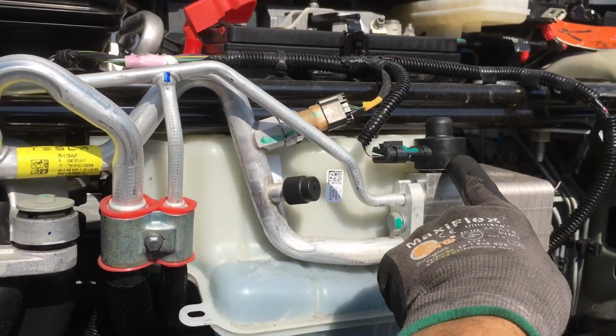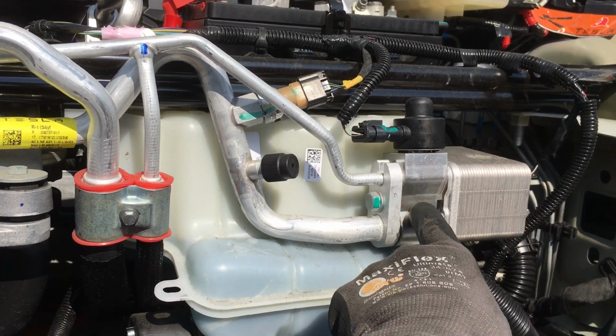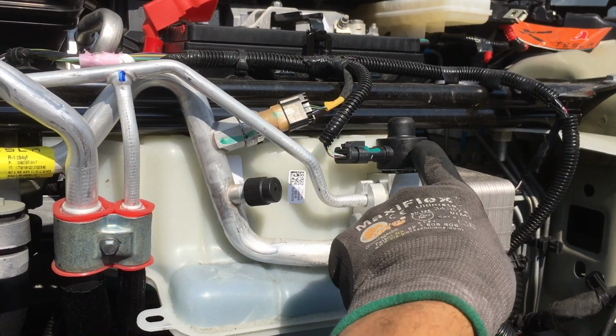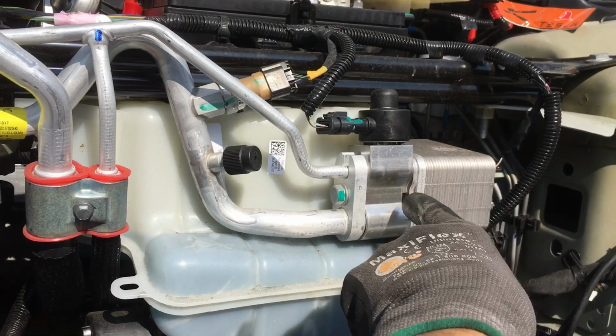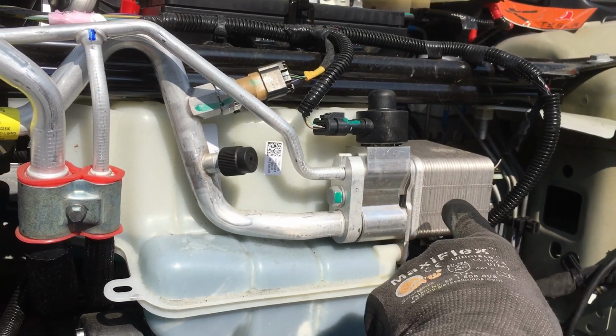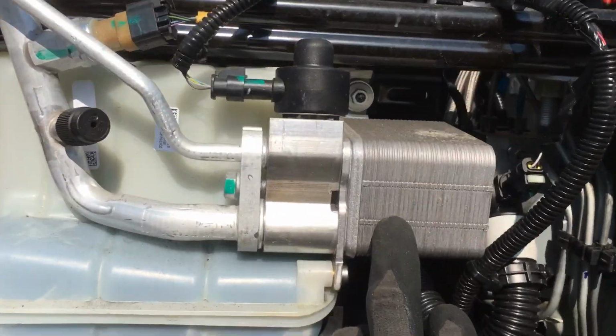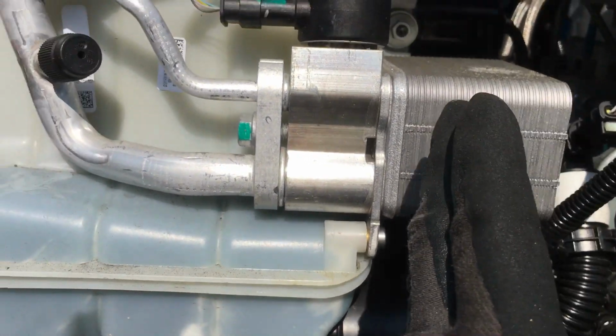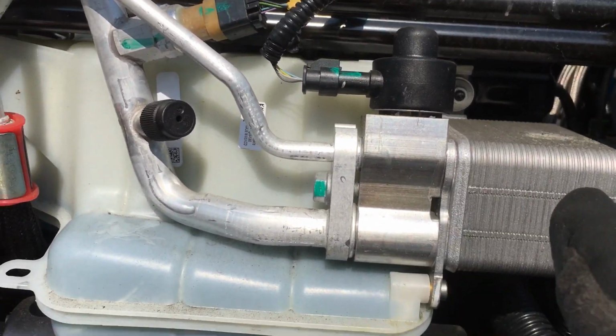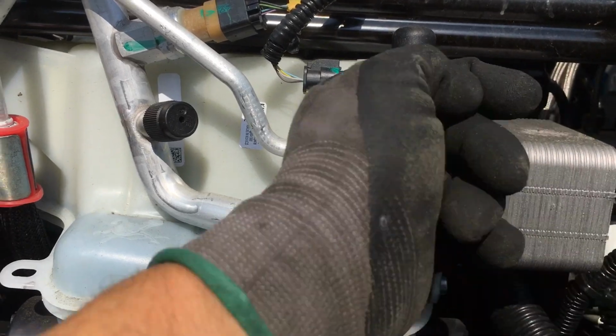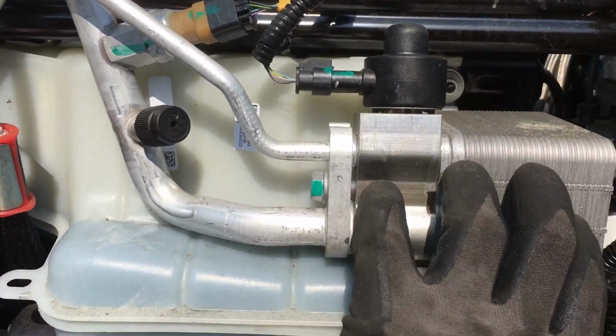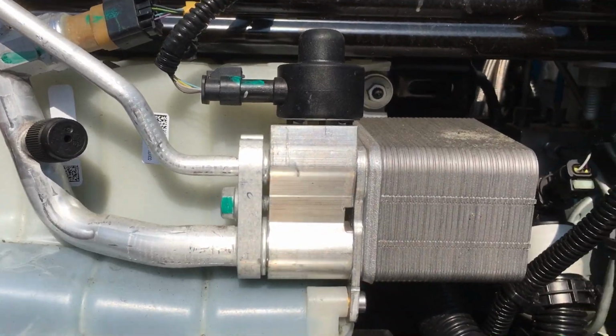Now this is an electronic expansion valve. This is not a thermal expansion valve. This is electronic, coming from your plate heat exchanger that has glycol on one side and refrigerant going down each passage. So every one of these little lines you see here is a passageway, and in one direction refrigerant goes, in another direction glycol, like that. They're exchanging heat right here.